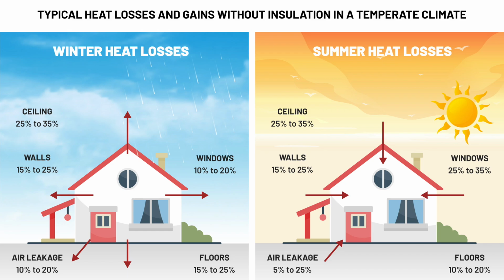So in the summertime, we have really high temperatures, especially in Kern County. We're in the triple digits. And inside the home, we like to keep them about 75 degrees. So we're looking at about a 30 to 35 degree temperature difference. So think about that. There's 35 degrees of temperature difference in the summertime from outside the home to inside the home. When you have two temperatures that are different, you're going to have heat transfer taking place. So we have to consider that temperature difference in that home.